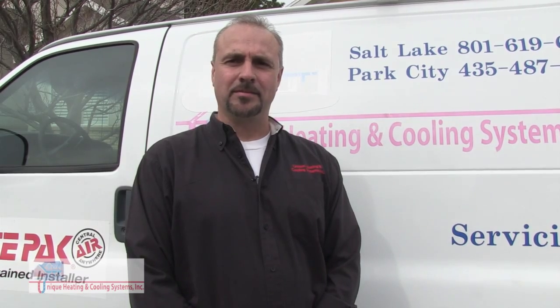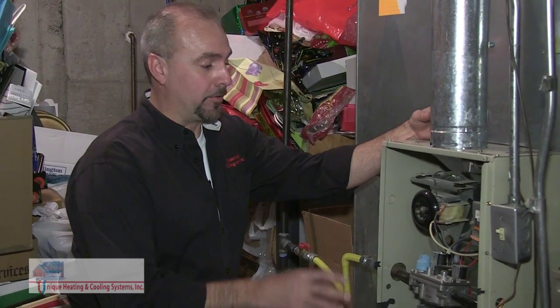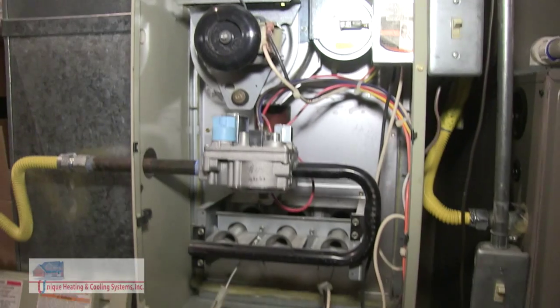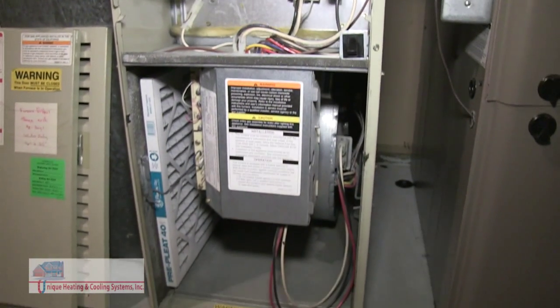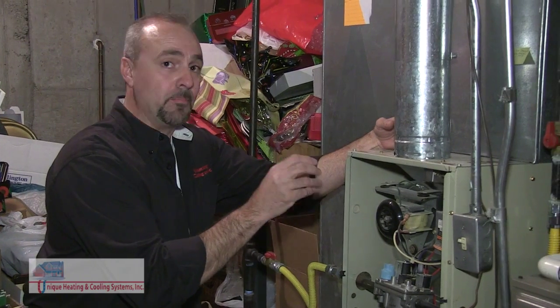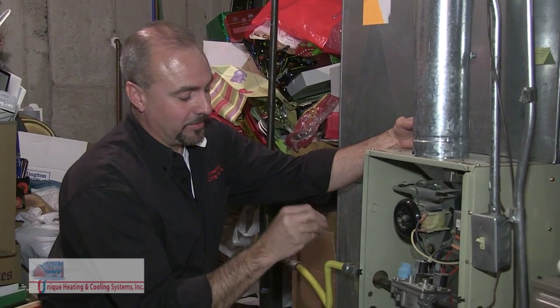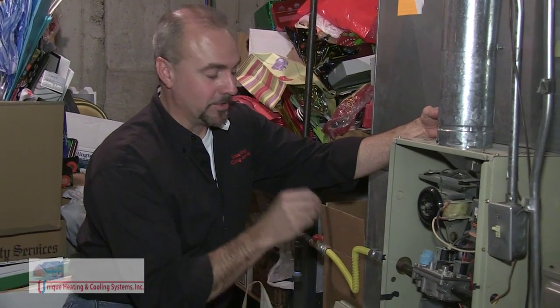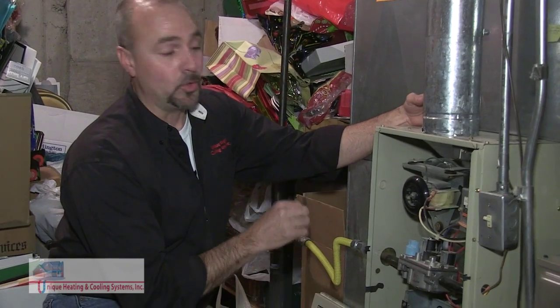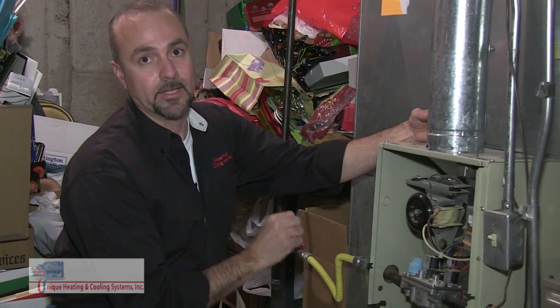of your filter changes. Three of the most common problems on a furnace are the inducer fan motor, the igniter, and the blower motor, all of which can be detected on a routine maintenance visit. The most common problem on a furnace is a dirty filter, and the most important thing that you can do for your furnace is to check it monthly.